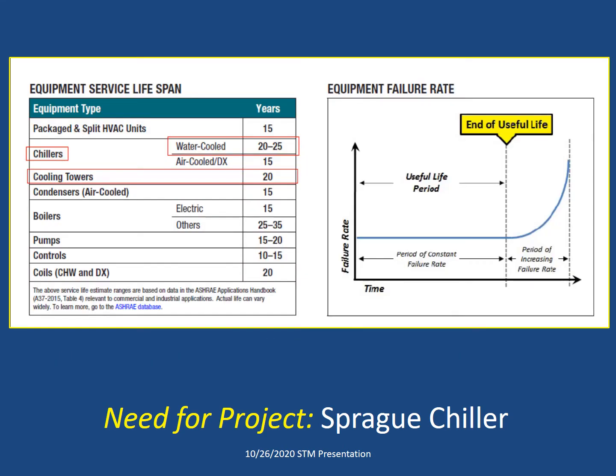ASHRAE is a reference standard that's used by mechanical engineers to evaluate equipment. You can see from this slide, which evaluates useful life or service life, that typically water-cooled chillers have a 20 to 25 year life, and cooling towers have a 20 year life. We have actually reached 20 years by summer 2021. And what happens when you get near the end of useful life is that the failure rate increases substantially.